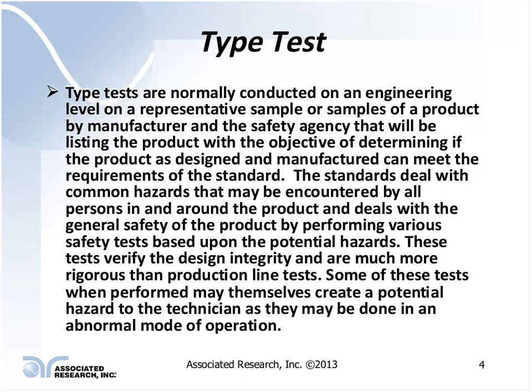One is the type test, or kind of an engineering test, that is conducted on a representative sample of your products based upon agency standards, where either your engineers or the safety agency that may be listing your product will actually conduct a bunch of tests on your product to make sure that it does comply to the safety standards that are designed for that type of product.